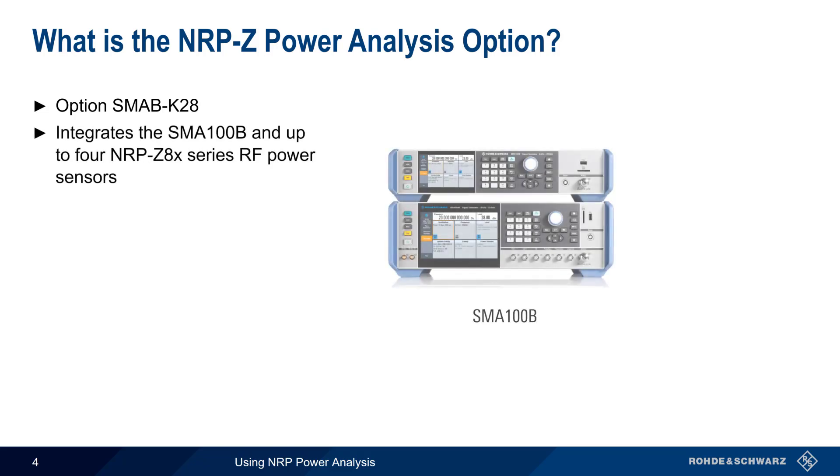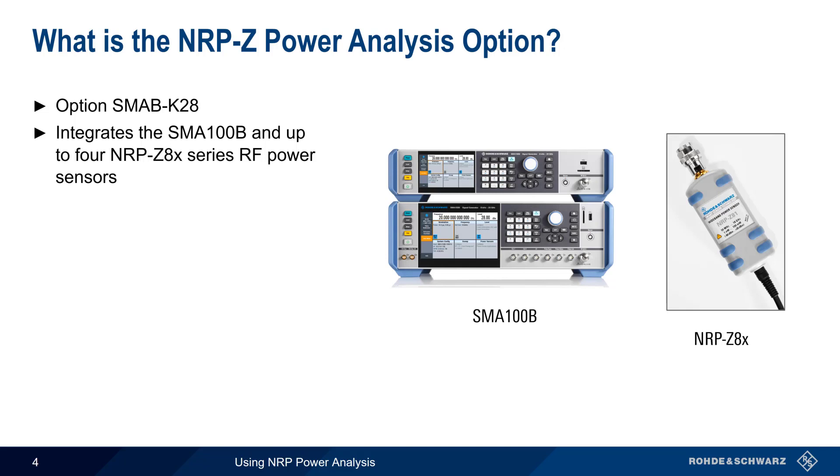The NRP-Z power analysis option, SMAB-K28, enables the integration of an SMA-100B and up to four NRP-Z8X power sensors. We can use this option to measure power versus frequency, power versus power, and power versus time. In the remainder of this presentation, we'll talk about each of these applications and show actual measurement results made with this option.